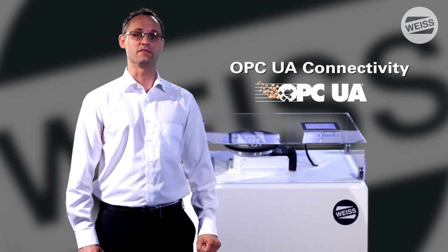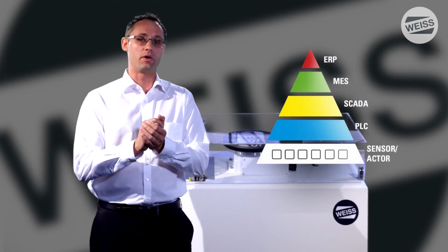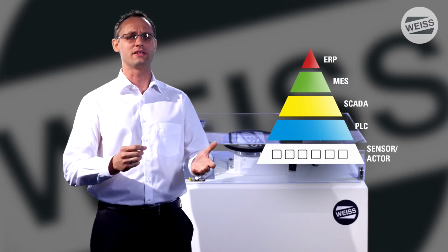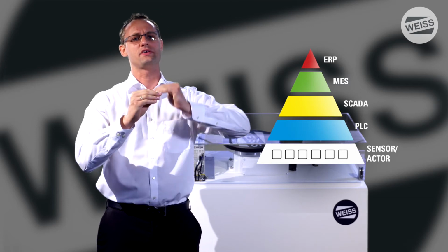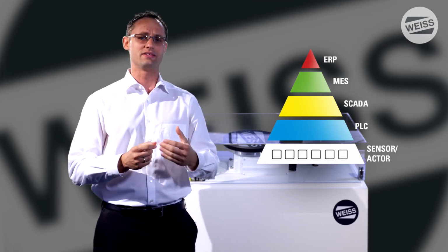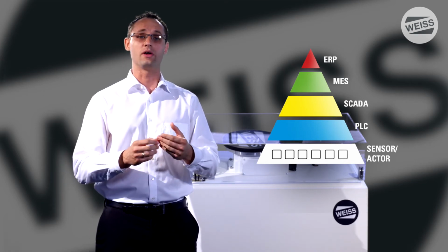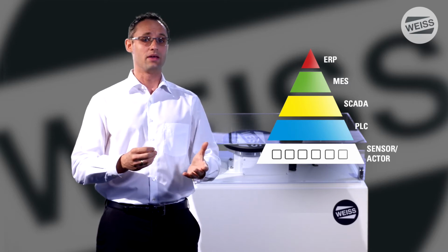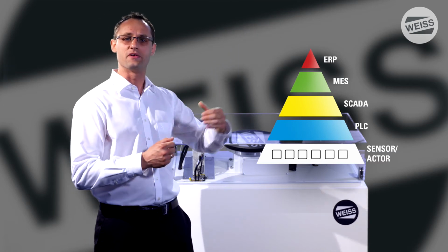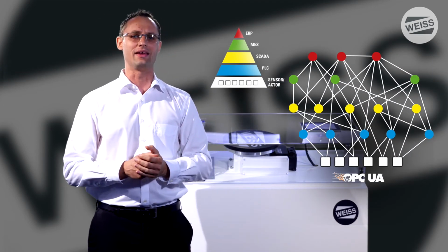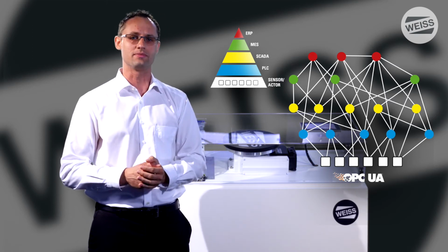Traditional field bus interfaces support only the traditional automation pyramid. If you want to monitor a new signal, you have to publish it in the fieldbus telegram, interpret that telegram in the PLC, then convert it to the SCADA layer, and only then send it over to the system actually needing it. But many of our products offer an OPC UA server. This way, you can simply jump over all of the layers of the classical automation pyramid, thus reading field-level data directly into your MES, ERP, or CMMS, shop floor maintenance management system.